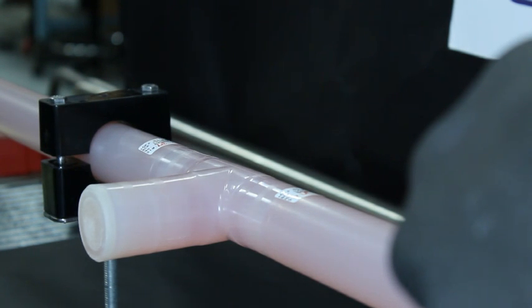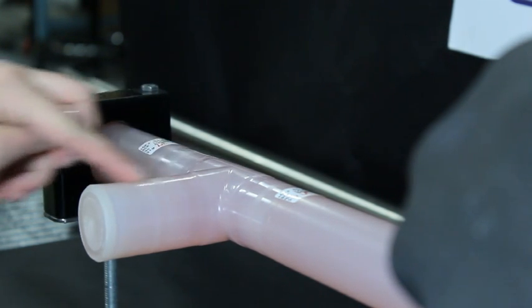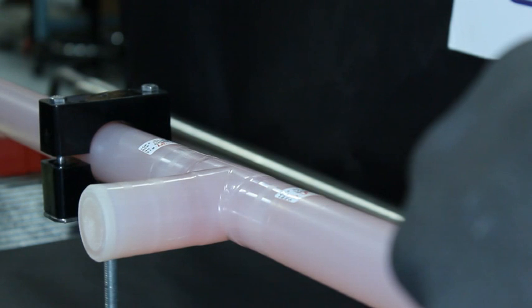Let's increase our flow rate and see what happens. As you can see, the air bubble becomes more sporadic and is moving faster than our leg. After about 5 minutes, this air pocket will be gone and we will have solved our problem by changing the orientation of our T.